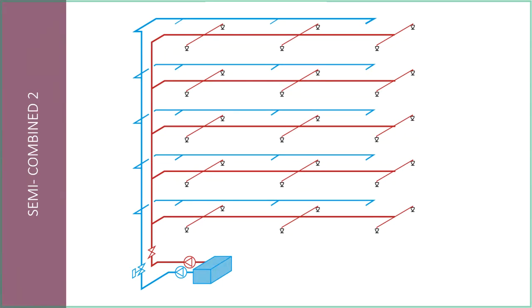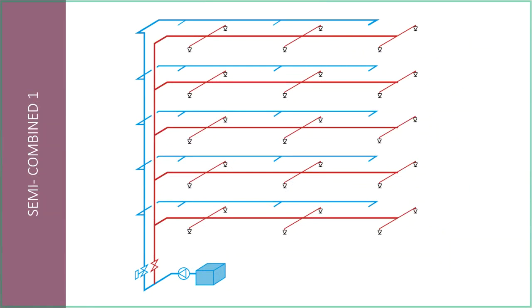Some people have said that they actually prefer to have a shared pump for the domestic and the sprinklers, on the basis that that pump is running all the time, so it's basically constantly being tested. Every time someone turns the tap, has a shower, or flushes the toilet, that pump is active. Whereas the sprinkler pump is mostly doing nothing in its lifetime. Also, if the pump fails, you're going to have residents complaining and telling you that the pump has failed pretty quickly. I take those points on board for sure. But obviously, any failure of that pump is going to knock out the sprinklers as well.